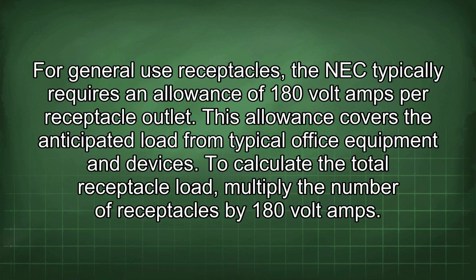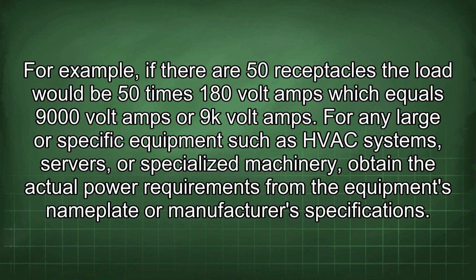For general use receptacles, the NEC typically requires an allowance of 180 volt amps per receptacle outlet. This allowance covers the anticipated load from typical office equipment and devices. To calculate the total receptacle load, multiply the number of receptacles by 180 volt amps. For example, if there are 50 receptacles, the load would be 50 times 180 volt amps, which equals 9000 volt amps or 9 kilovolt amps.